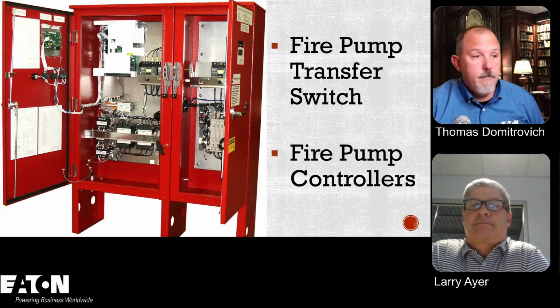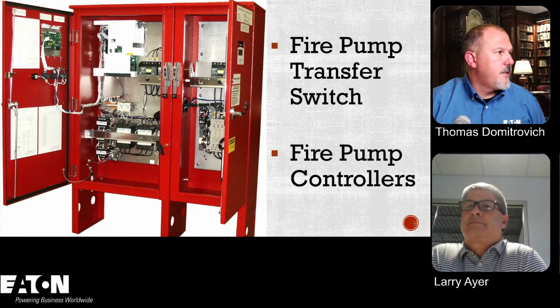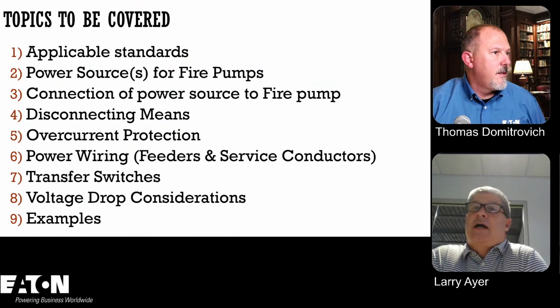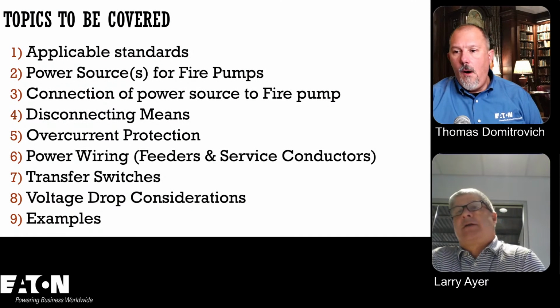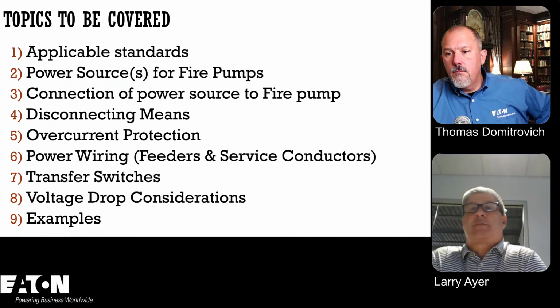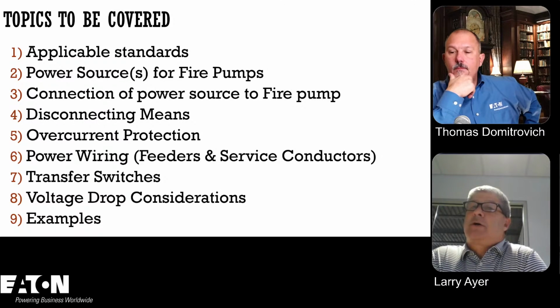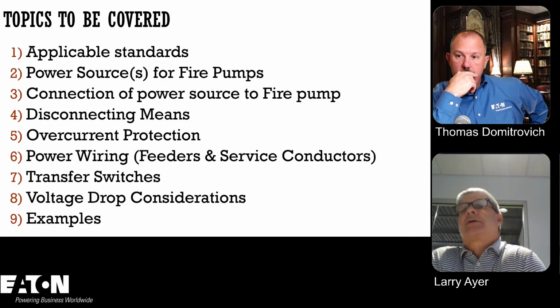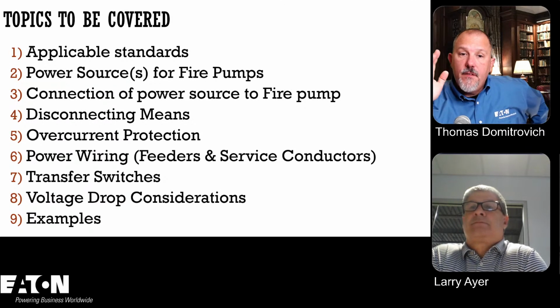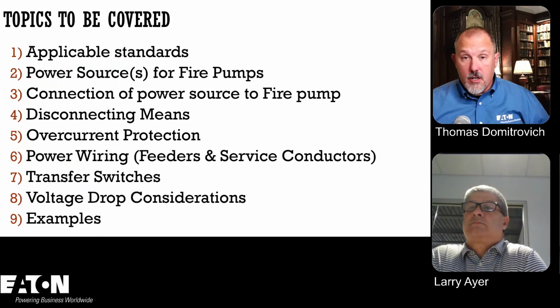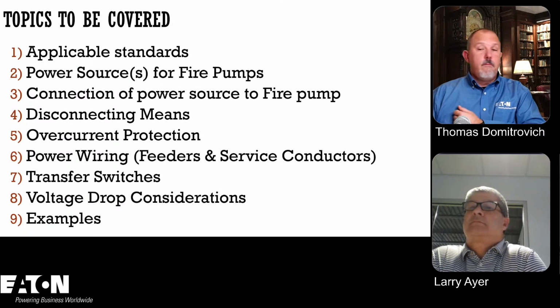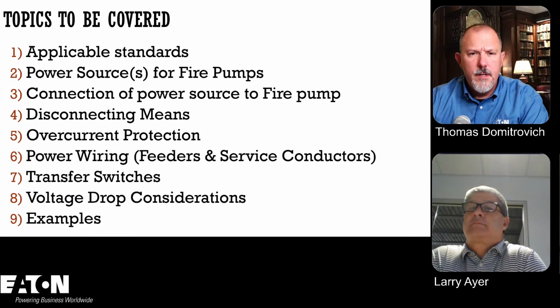Yep. Gotcha. Good questions. I've seen people not even back those up with generators. You don't have to put a 2-hour rating on those. It's just to maintain pressure and things of that nature. If that jockey pump's not working, that doesn't mean your fire pump is not going to work, is what your point is. Correct. Yeah. All right, that's a good point too.